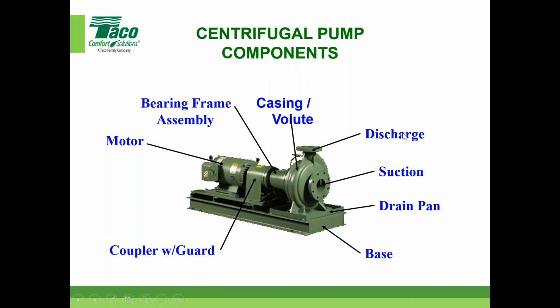There's the suction, there's the discharge, casing, volute, wet end, whatever you want to call it. The bearing frame, so this pump has 2 shafts. One shaft attaches to the impeller, and then you have the motor shaft. I'm going to have another drawing that shows you where there's actually a space between them too. But the bearing frame helps support the impeller shaft as it comes out. And we'll talk about that in a little more detail.